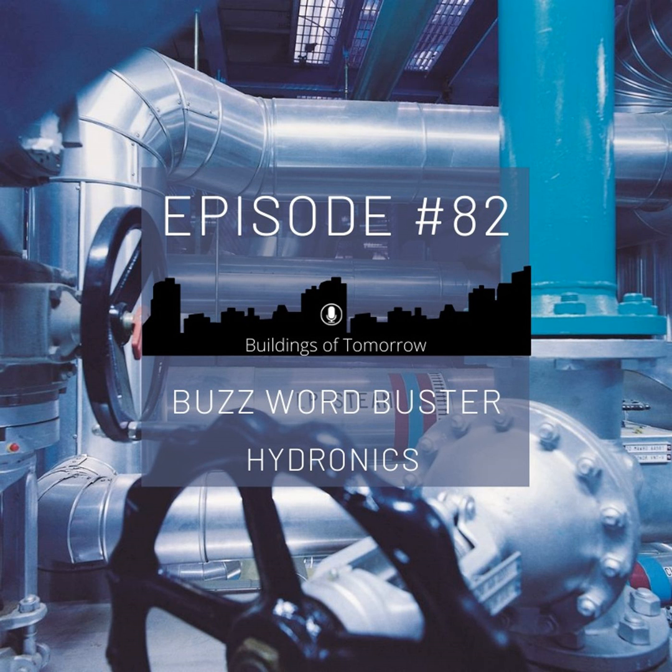We always have exactly what we need out there at any given consumer, because we always check which consumer has the biggest demand, and this one then drives the pump speed and with that the pressure that the pump provides. And this is the most energy efficient way of doing it. But of course, it needs a communicating building automation system, because somehow we have to get the information from the different consumers throughout the building.